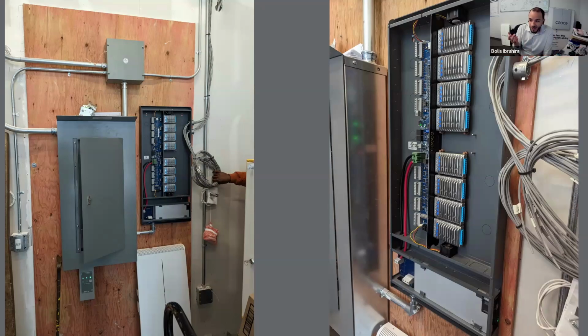Yes, this is to code — the inspector comes and sees it, and yes, this is to code. This is low voltage cable, you can treat this like they use J hooks. Think of this as Ethernet cable — if this was data cable, would this be appropriate? A lot of people would say yes. From a code perspective it's electrically safe, virtually free of any shock or fire hazard. So it becomes up to the installer and the customer how much money they want to spend on appearances and the rest. But is this safe? Yes. Is it pretty? No, it's not, and there are probably better, cleaner ways to do this, as I'll show you. But yes, this totally is safe, and the inspector will come on site and take a look at this stuff prior to closing out the permit.